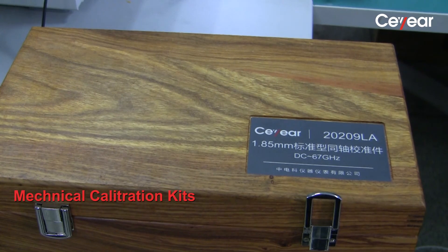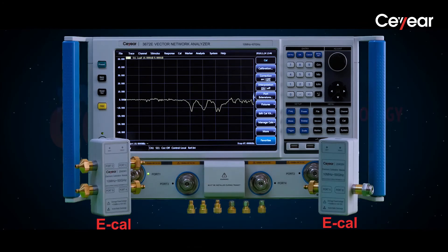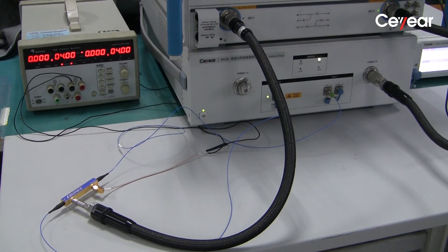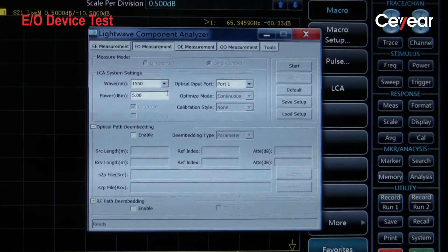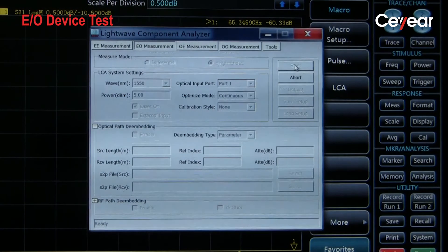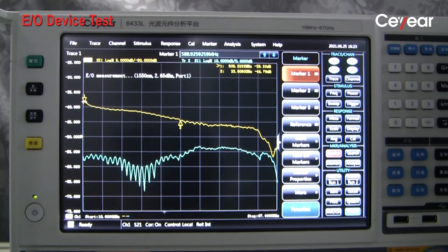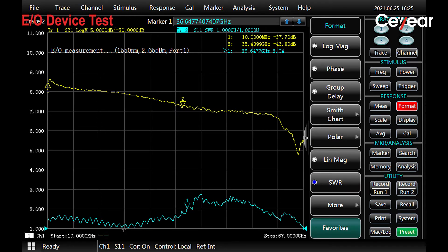After warm-up, we calibrate the VNA using a mechanical or electrical calibration case at both cable ends. Now let's test the electro-optical modulator, an EO device. We connect the system and modulator as shown on screen. In EO measurement mode, after setting the wavelength and output power, we press the start button. The system will first auto-calibrate the channel and then display S21 and S11 on screen. We can see that the device's 6 dB bandwidth is about 35 GHz.